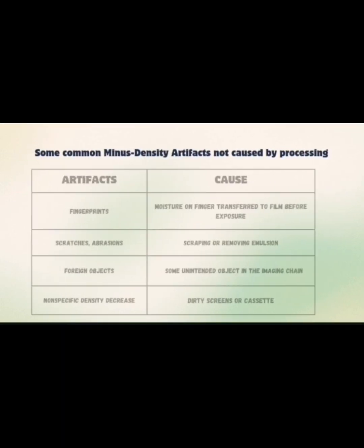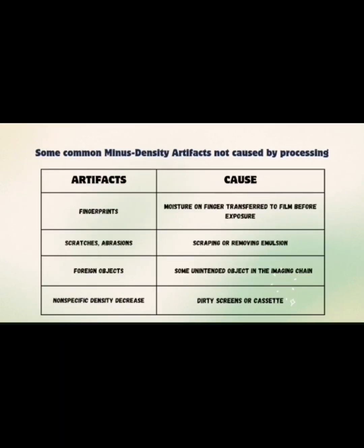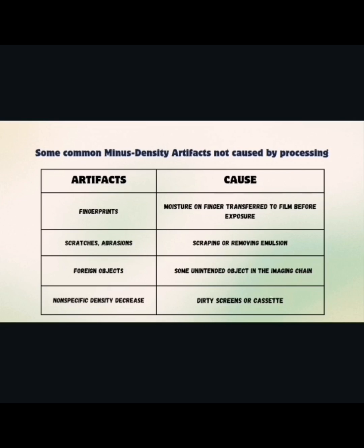Some common minus density artifacts not caused by processing. Fingerprints. The cause is moisture on a finger transferred to the film before exposure. The second is scratches and abrasions. The cause is scraping or removing emulsion.